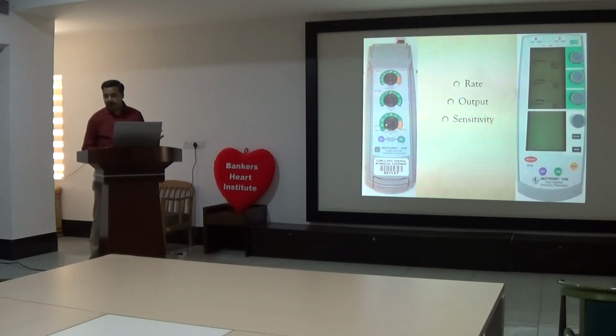So in that case, we set these parameters of sensitivity at a rate of, say, 0.5. So any inherent cardiac activity which has a current of 0.5 millivolt will not be paced. That will be sensed. The pacemaker will sense that there is an inherent cardiac activity. The pacemaker will inhibit itself. The pacemaker will not pace for that particular beat.